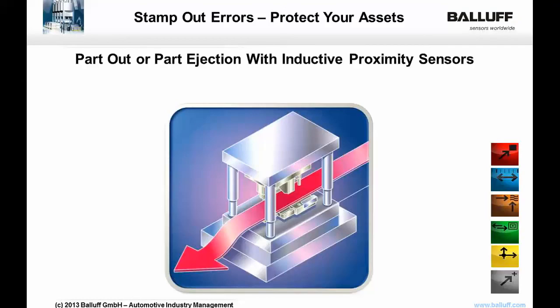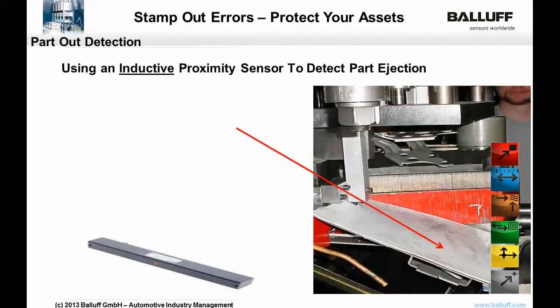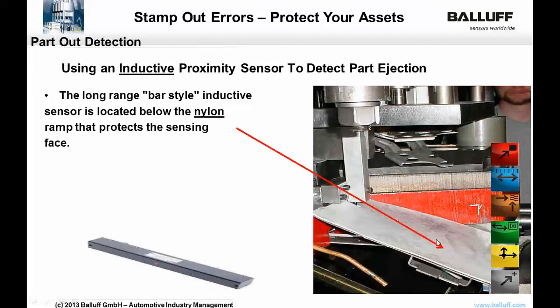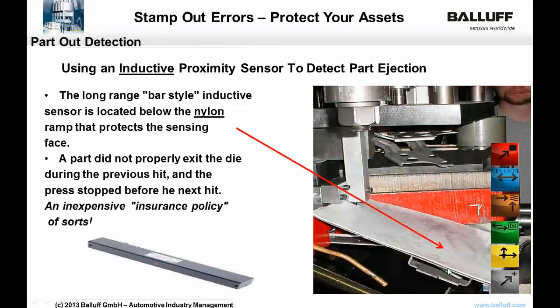So we'll look at some part-out ejection examples using inductive proximity sensors. In this particular case, we're using a bar-style inductive proximity sensor. Here you can see the part being ejected out of the press, and it's being placed onto this slide. This is a non-conductive material. So as that part slides down this ramp, the sensor is mounted under here, and it will indicate that the part has been correctly ejected out of the press. As mentioned here, placing this device here is an extremely inexpensive insurance policy of ensuring that the part has ejected the press before a second strike occurs.